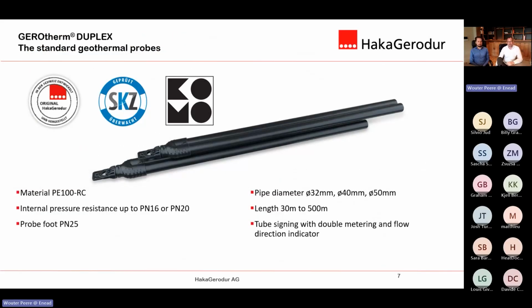So here we come to the standard duplex probe. The material is PE100-RC. We manufacture them in PN16 and also PN20. The U-bend is always PN25, doesn't matter if it's PN16 or PN20. We have different diameters: 32, 40, and 50, with lengths up to 500 meters. We also do customized products, but it doesn't make sense to go deeper with a cylindrical probe because we have the conical probe, which has much better efficiency because of the conical style.